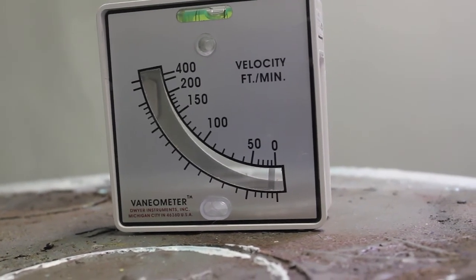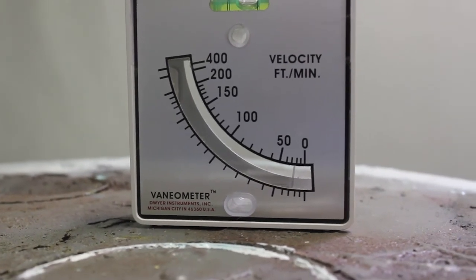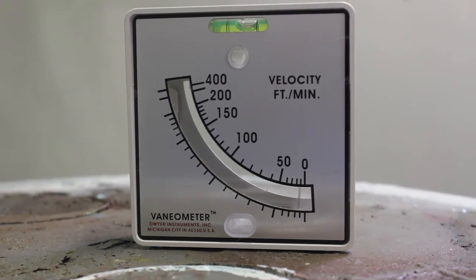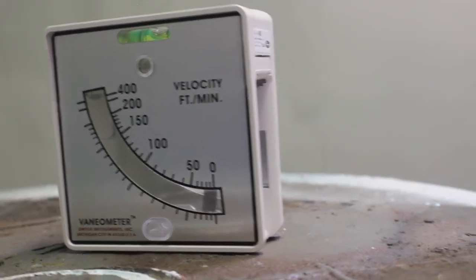Now, if your airflow isn't where you want it to be, there's a variety of things to check. First would be to check your filters to make sure they aren't overly dirty. Dirty filters slow down airflow in a paint booth as they load up with paint.